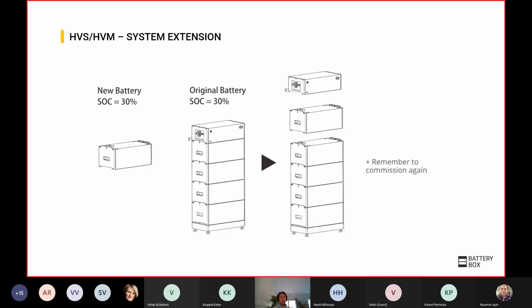You will see that you are getting a lot less energy than we were getting even before the battery was added. In order to avoid that, make sure that you only add new batteries when you are close to 30%. 25, 30, that range will be okay. So you can discharge the battery, and when it hits 30%, stop it there, or the opposite. When it's charging, stop at 30%, and then you can add the module in.